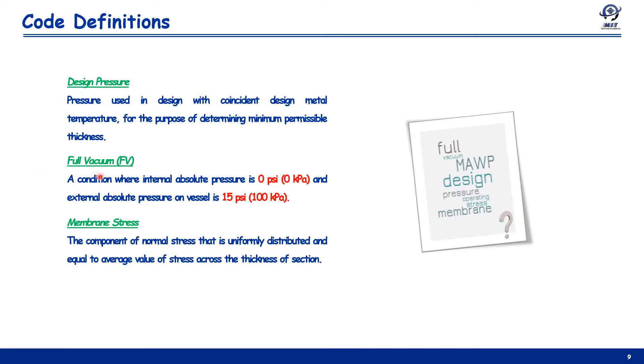Full vacuum (FV), as shown even on vessel nameplates, is a condition where the internal absolute pressure is 0 psi (or 0 kPa) and the external absolute pressure on the vessel is 15 psi or 101.3 kPa. Membrane stress relates to the normal stress component that is uniformly distributed and equal to the average value of stress across the thickness of a section. This applies specifically to thin sections because stresses can be safely assumed not to vary significantly across the thickness.